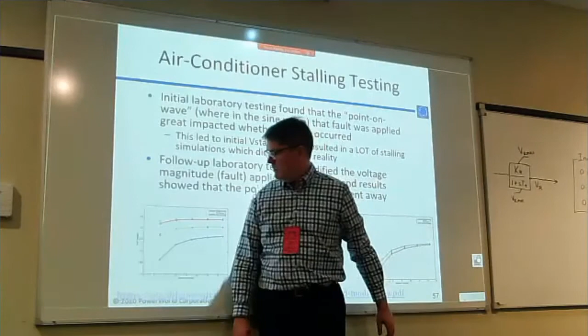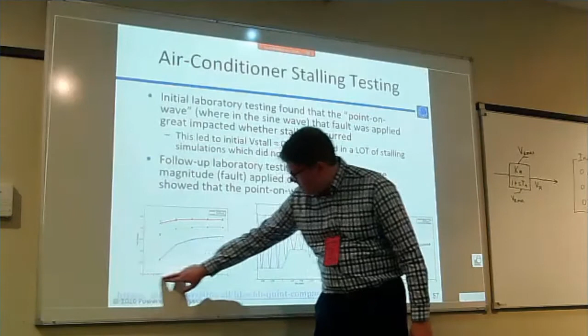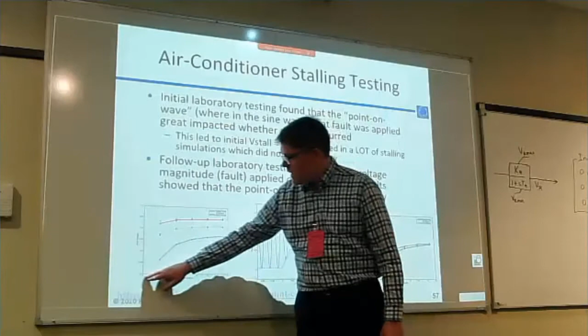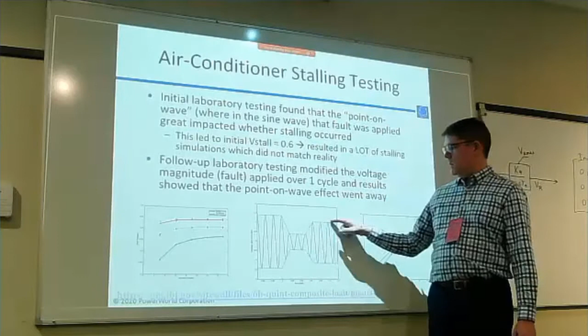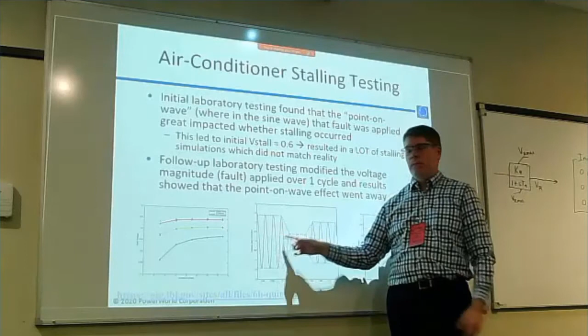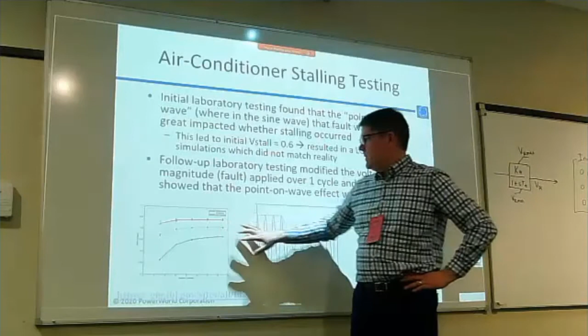And the initial testing that folks did here in this building, let me hide this, just look at this to start. So in about 2012, they're testing where this is, it's hard to see here, but this is voltage. No, sorry, this is time. Time versus voltage. So they would run a test where they were actually looking at the three-phase waveform, and they would fault it either at the peak, somewhere in the middle, or at a zero crossing. So they'd actually set up their test so they'd apply the fault exactly at a particular point on the wave. And so it would actually go to zero instantly and then recover instantly. And what Steve found in the lab was, depending on whether he faulted at the peak or the zero crossing, he got very different results as to whether it stalled or not.